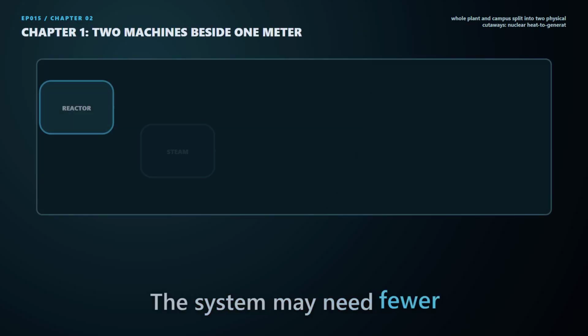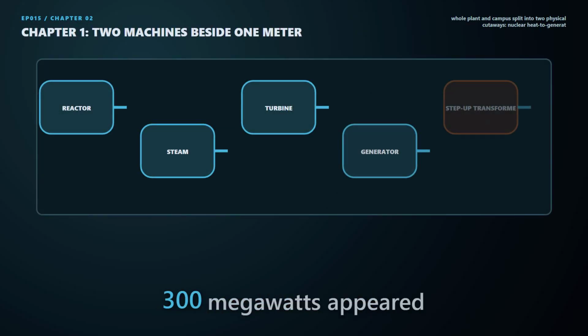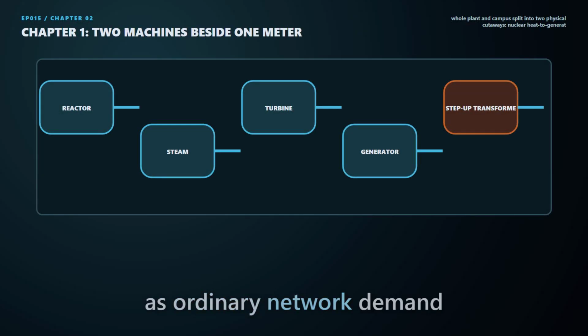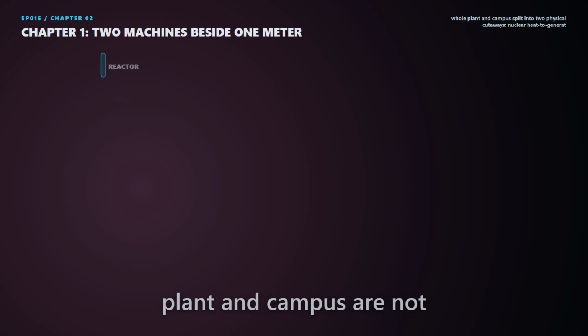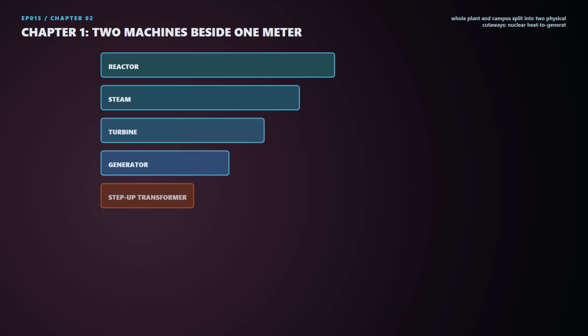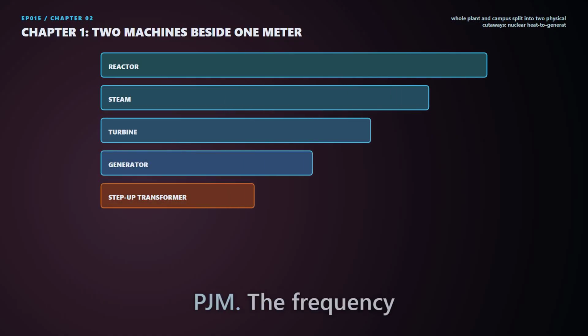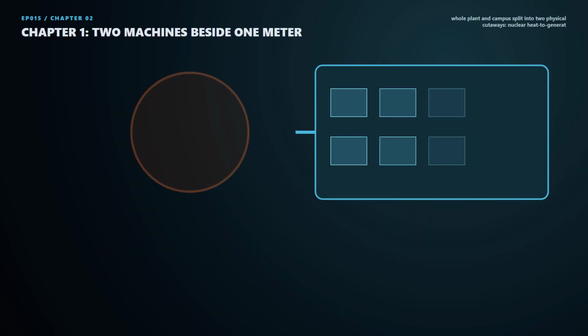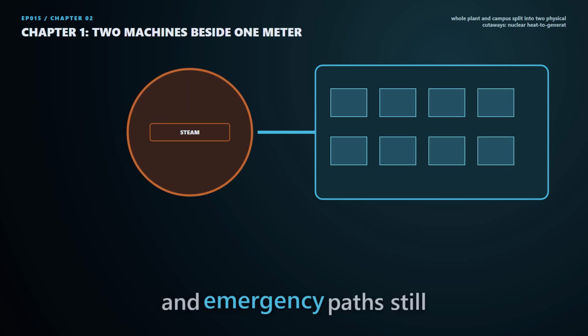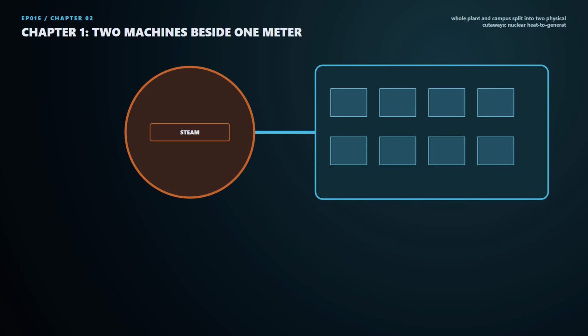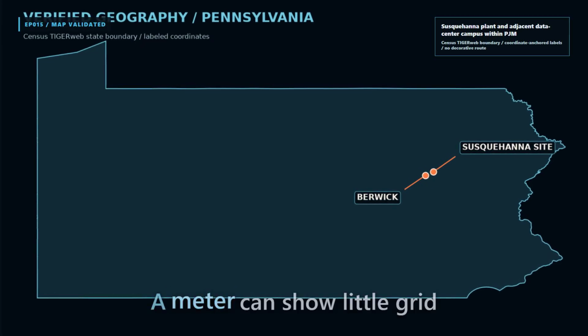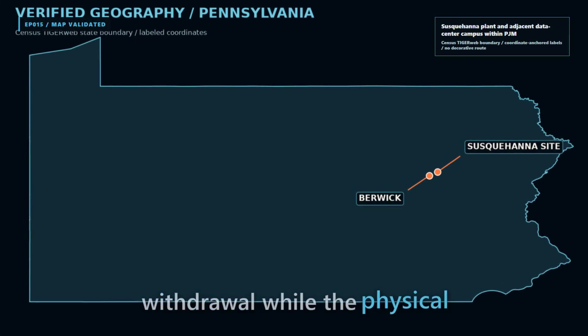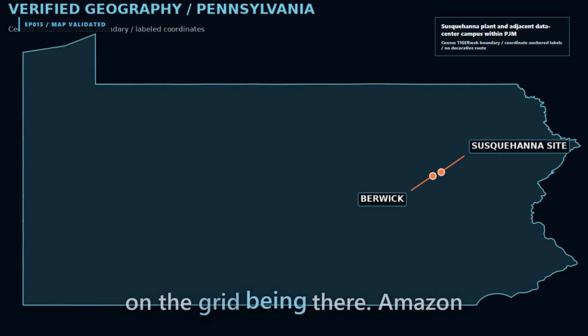The system may need fewer upgrades than if the same 300 megawatts appeared as ordinary network demand somewhere else. But the plant and campus are not an isolated island. They remain synchronized to PJM. The frequency reference, contingency support, market dispatch, and emergency paths still come from the larger system. That is the central tension. A meter can show little grid withdrawal while the physical arrangement still relies on the grid being there.